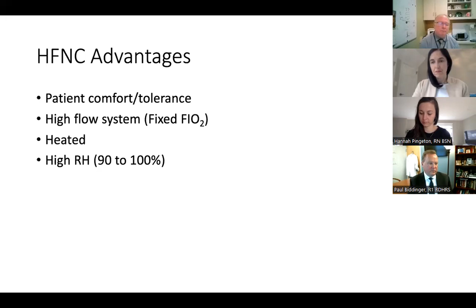Unlike some of the low flow systems where patients take a breath in and it mixes with the supplemental O2, and you really have no idea what their O2 requirement is, which can be a strong indicator of their disease severity. They have to be heated and they have to be humidified. The device we use is the same humidifier we use on our ventilators, and it provides relative humidity of 90 to 100% at these high flow rates.